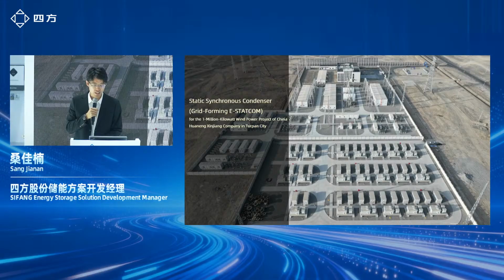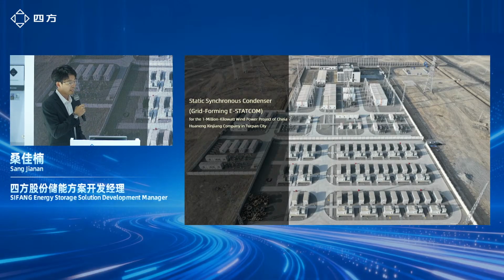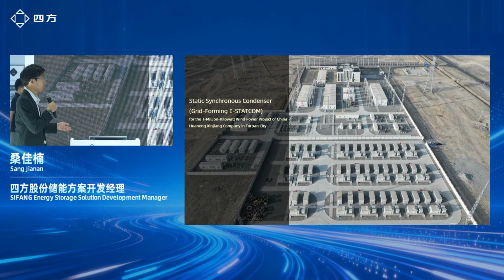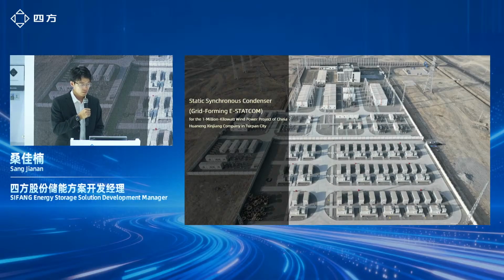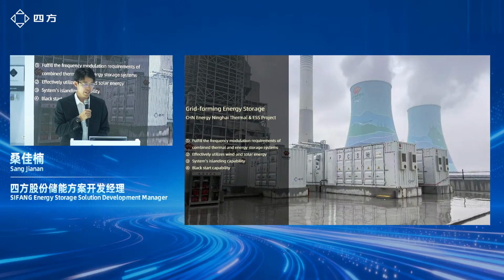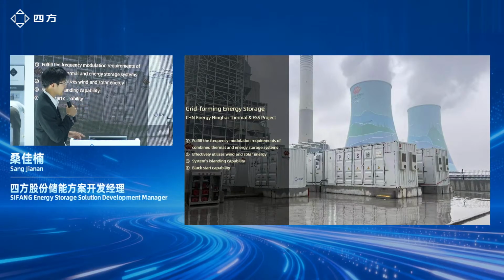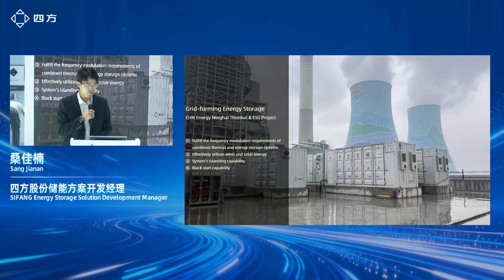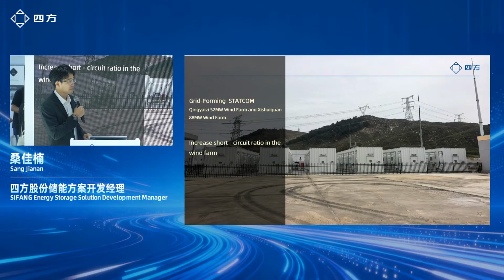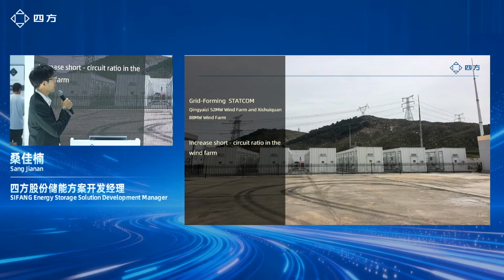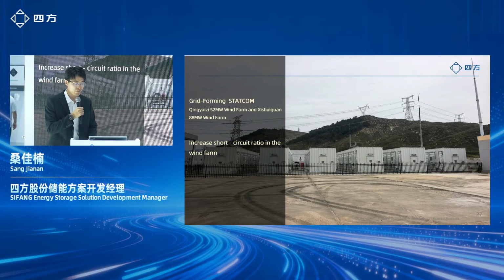Okay, here are some project references. This project is about Grid-Forming STATCOM. Here we adopt a 100 megawatt STATCOM to support the voltage and the inertia. This is used in Xinjiang company for the 1 million kilowatt wind power system. And here is the CHN Energy Ninghai Thermal project. For this project, we adopt a 5 megawatt hour Grid-Forming BESS system to participate in frequency modulation and voltage modulation. And here the Grid-Forming STATCOM, this is a traditional one. We adopt 50 megawatt to increase the short circuit ratio in the wind farm.